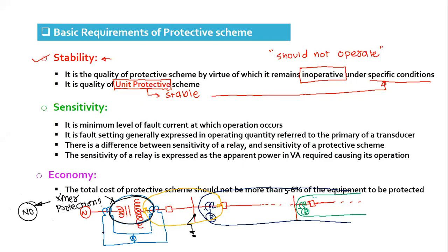It will create misleading information. Suppose there is a fault on the bus bar and the transformer relay operates. The operator may find that there is a fault in the transformer, and you will try to figure out what the fault in the transformer is, if the transformer relay operates.